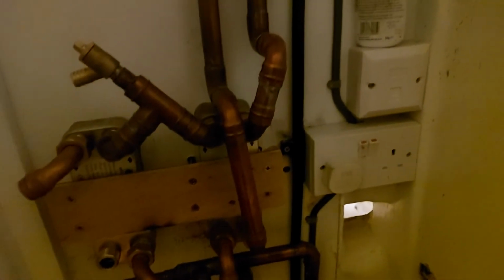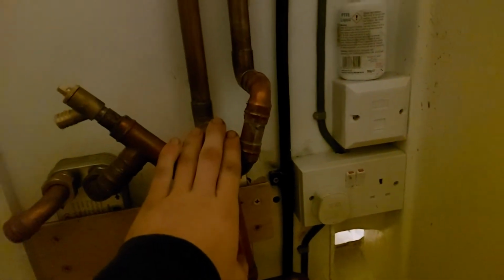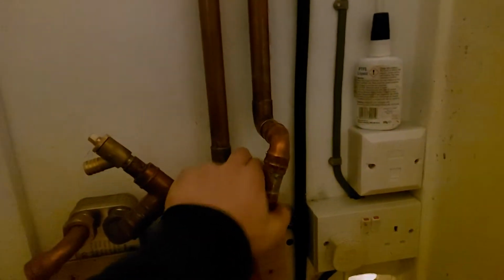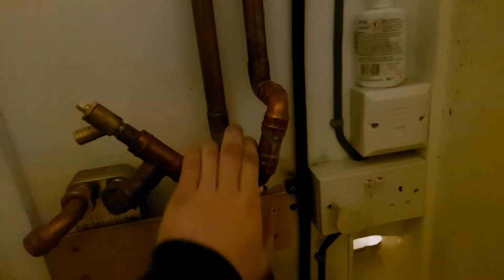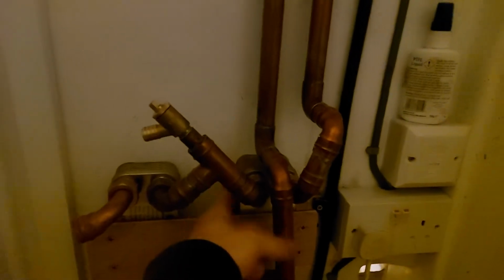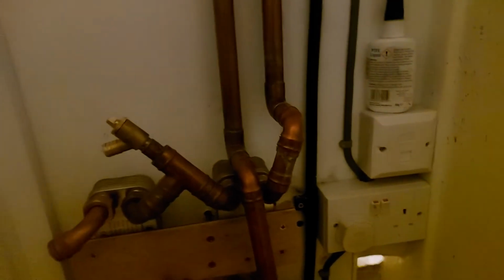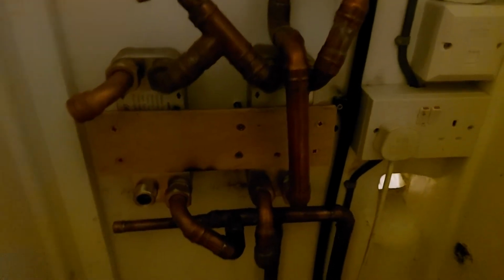So there's quite a big temperature difference there, and that means quite a big inefficiency. So what I'm probably going to have to do is use this one for the hot water, because when the cold water comes in it's really cold, so you're going to get more heat transfer power since the temperature difference is much larger.